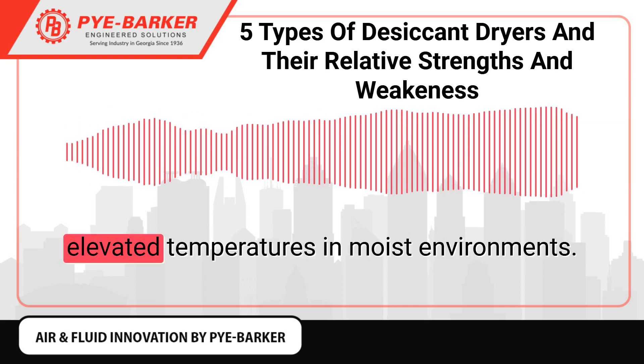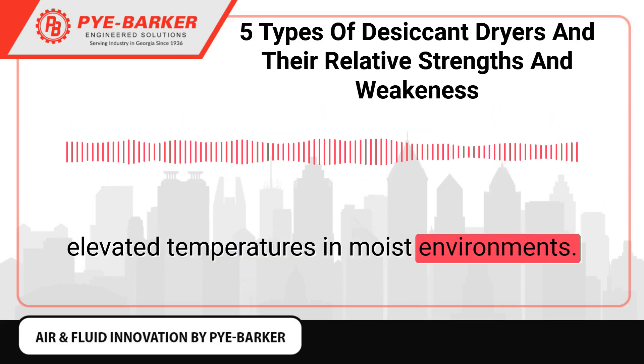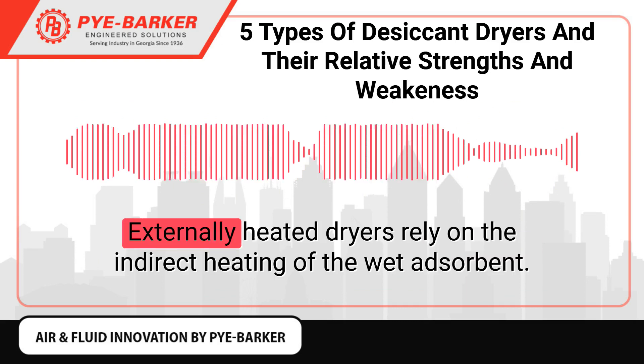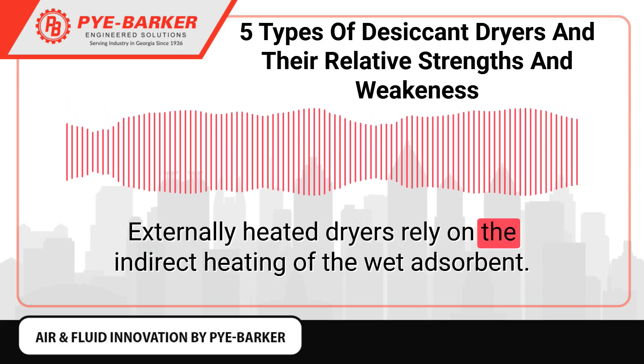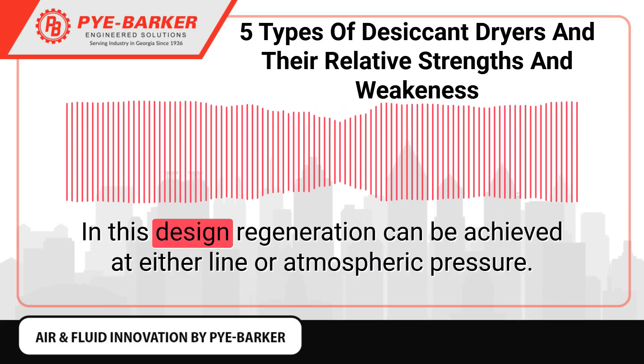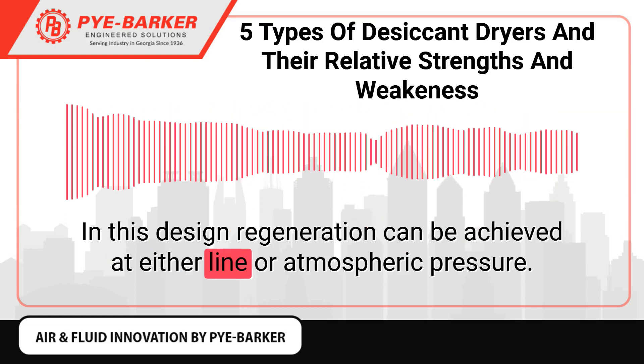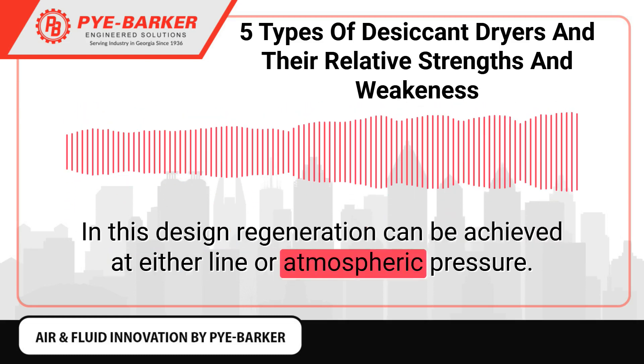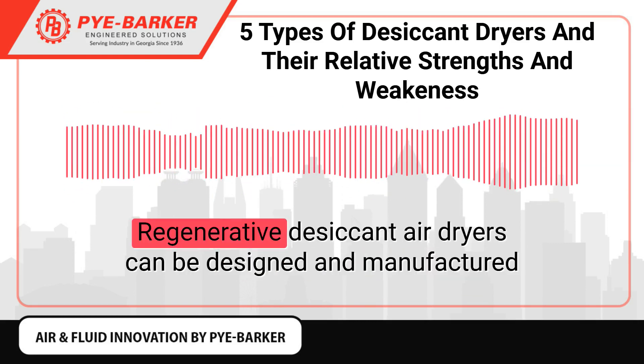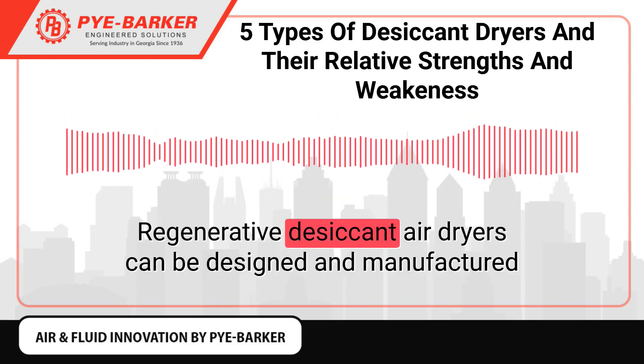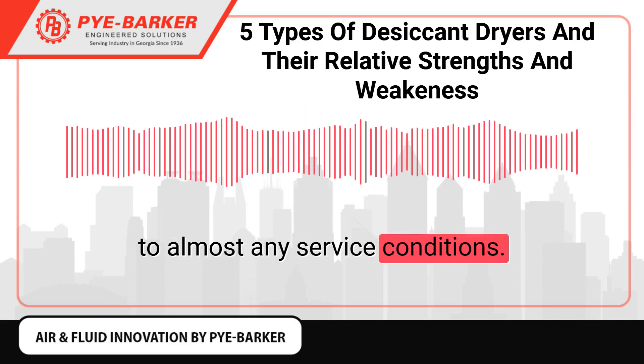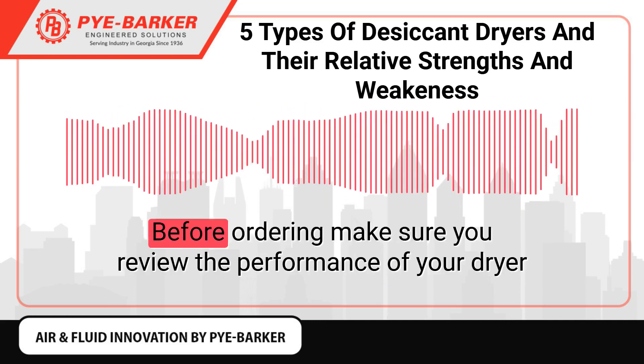Externally heated regenerative dryers rely on the indirect heating of the wet adsorbent. In this design, regeneration can be achieved at either line or atmospheric pressure — atmospheric pressure being the more efficient option. Regenerative desiccant air dryers can be designed and manufactured to almost any service conditions.